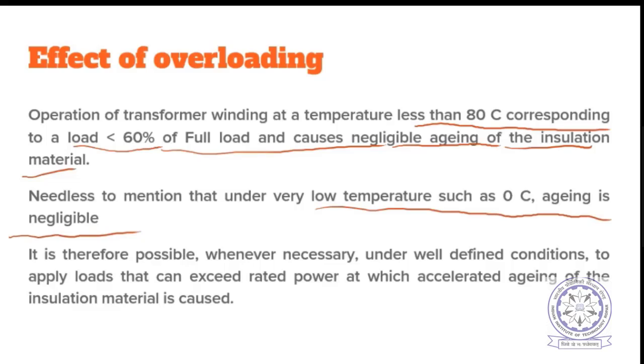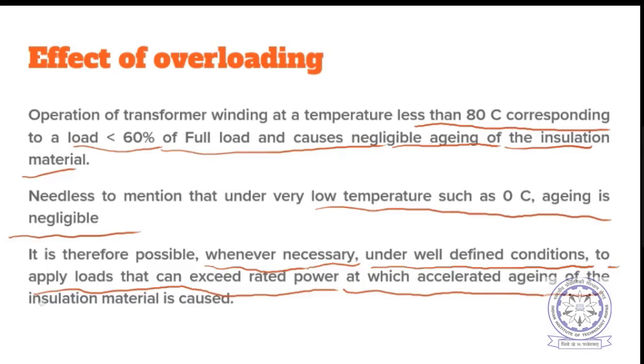So if that is so, then occasionally we can overload the transformer. Therefore it is possible, whenever necessary, under some well-defined conditions, to apply loads that can exceed the rated power, at which some accelerated aging of the insulation material is caused. So not continuously, but under some conditions whenever necessary, the transformer can be overloaded, because under normal conditions, if the temperature is less than 80, if it is less than full load, then the aging is almost negligible. So under certain conditions we can always overload the transformer. That's what it means. Then what are the types of overloads that will occur?